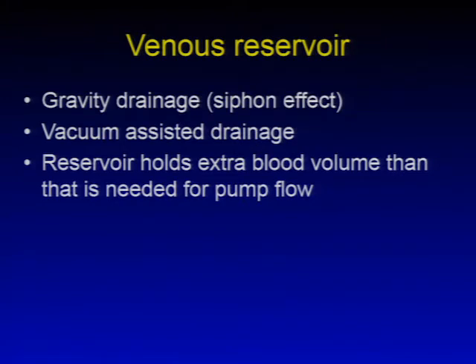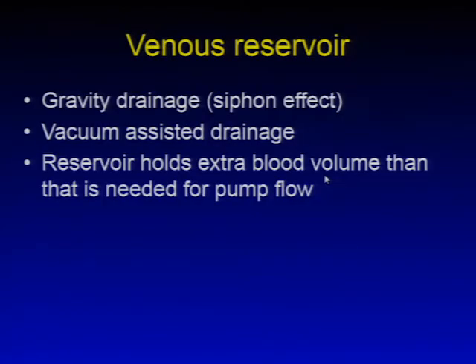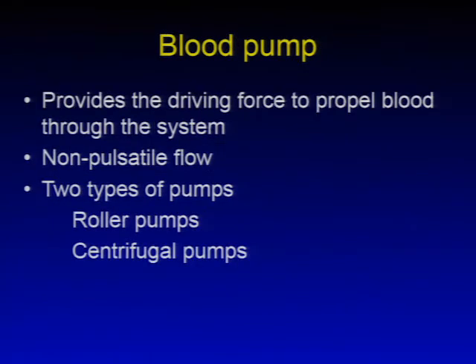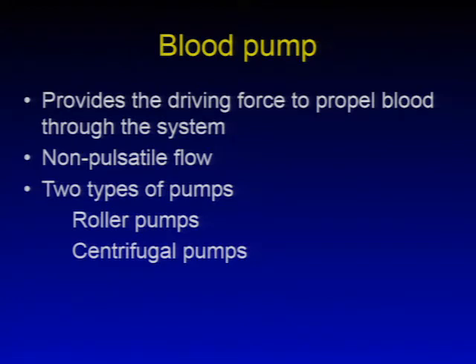The venous reservoir is the first key component of the CPB circuit. Venous drainage is typically by gravity and siphon effect; vacuum-assisted drainage can be used to assist drainage. The basic function of the reservoir is to hold extra blood volume beyond what is needed for pump flow. The second component is the blood pump. There are two types: a roller pump and a centrifugal pump. Most pumps provide non-pulsatile flow as the driving force to propel blood throughout the CPB system.